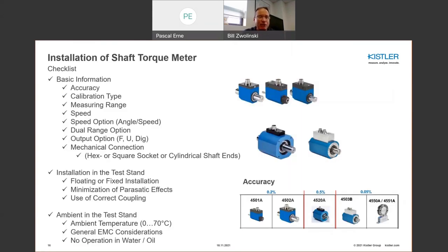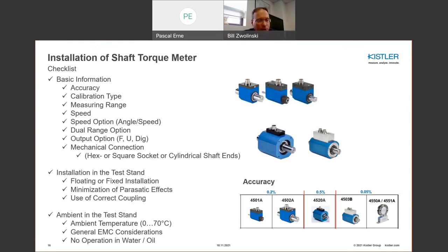For shaft torque meter installation, the first decision is accuracy. The accuracy class ranges from 0.05% to 0.2% to 0.5%, so there's a wide range. Key selection criteria also include calibration type, measuring ranges, and speed capabilities. Nowadays you can get a dual range option — there may be a large startup torque followed by a much lower running torque, allowing you to optimize your measuring range. There are floating and fixed installations for shaft torque meters, and you must look at coupling and parasitic effects. Temperature is usually the most common error source in almost any measurement.